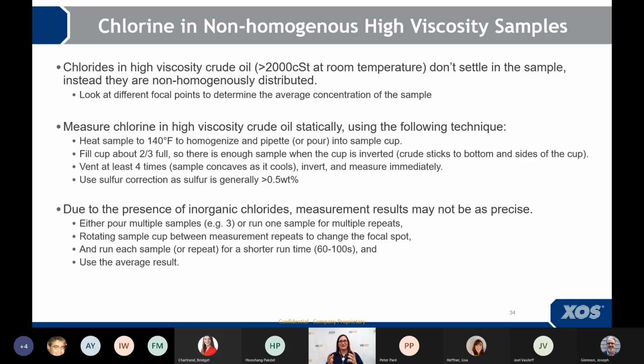And I'm doing this with my hands because what you're going to do is, when you set your cup up, you're going to do very similar to what you did before. You're going to set that repeat delay for the 10 seconds, and you're actually going to reach in and rotate the cup. That is enough to get it to look at a different focal point. You do this for about 3 measurements, anywhere from 60 to 100 second measurement time, depending on the concentration of the chlorine. And when you do that, you're looking at these different focal spots, and you get a printout with the statistics already computed for you.